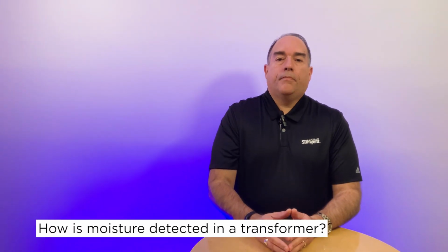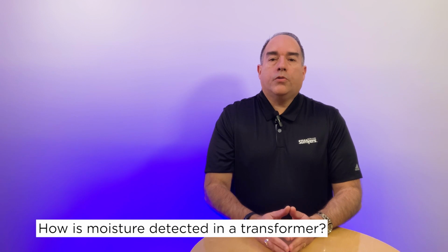This is supposed to be the long accepted fact that doubling the moisture content in a transformer can cut its life in half. Okay, so how is moisture in a transformer detected? Moisture is more often detected by taking an oil sample from the transformer and completing a test called Karl Fischer in our laboratory. This test determines the ppm of water in the transformer, and by using the temperature of the oil at the time of the sampling, we can calculate percentage of saturation, and this figure tells what content of water is found in the oil in the transformer.